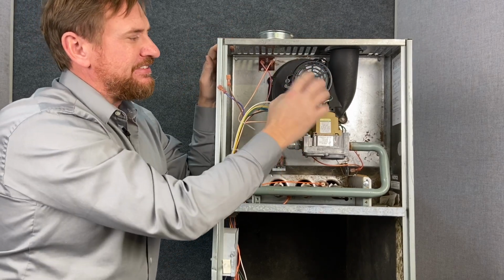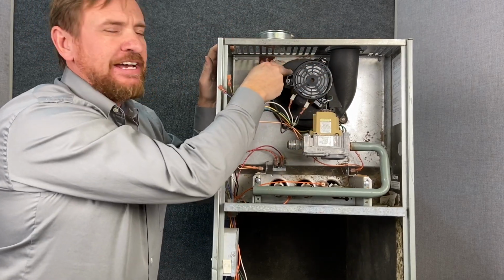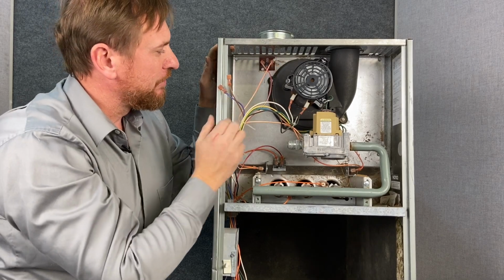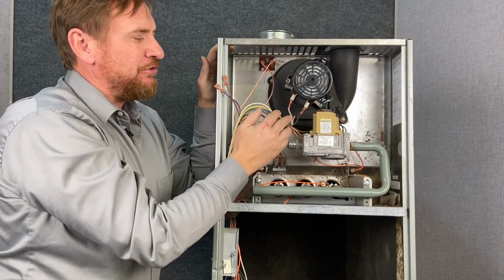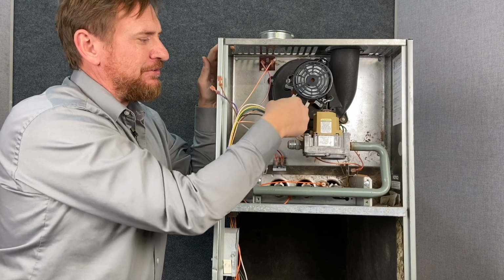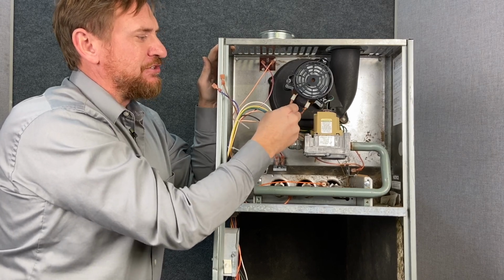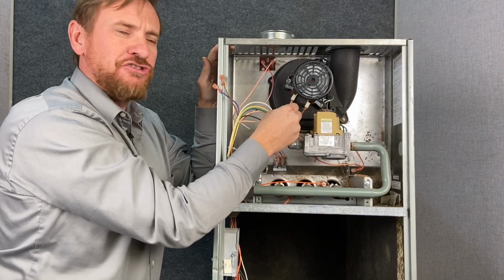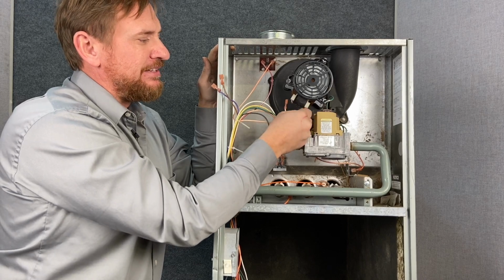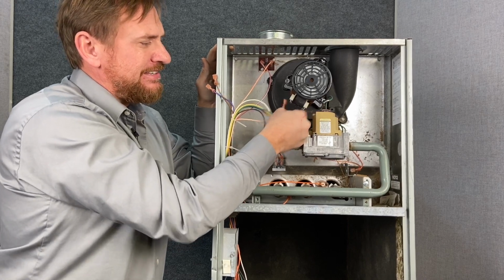This little fan on this side keeps the motor cool, but on the other side it's another blower. So what we're going to do next is we're going to go ahead and take that off. There's going to be 2 wires here. Oh, and that one was very loose. Number 1 cause of electrical issues is loose connections, and that connection is extremely loose. So that's something we would want to tighten up. This one's good and tight. That's how we like it.